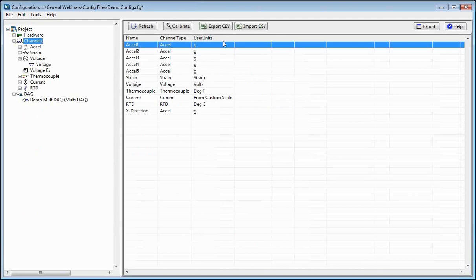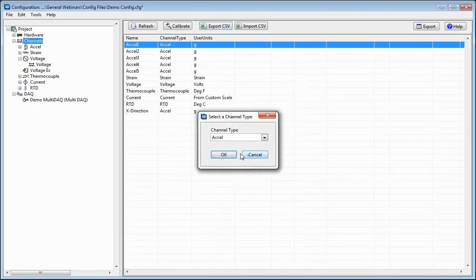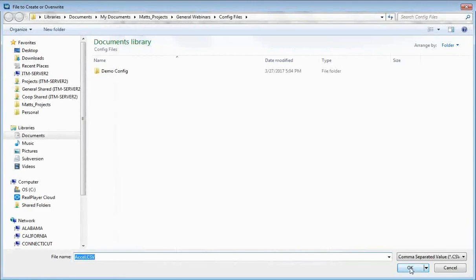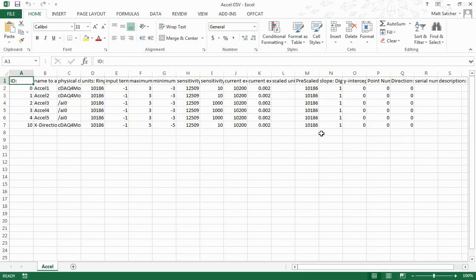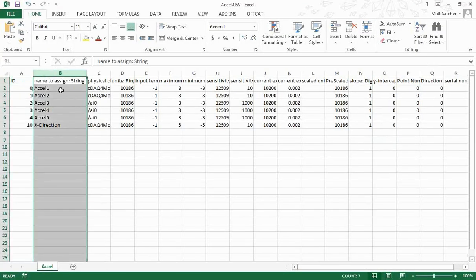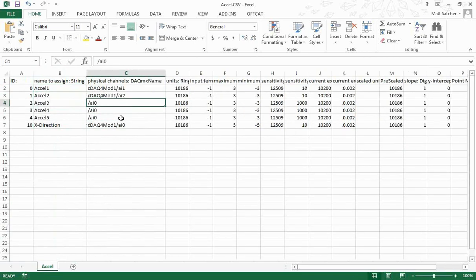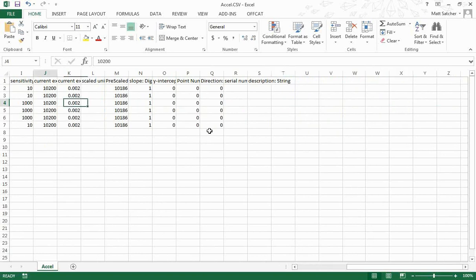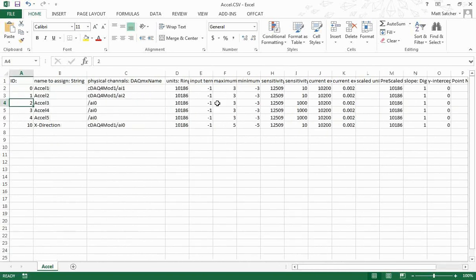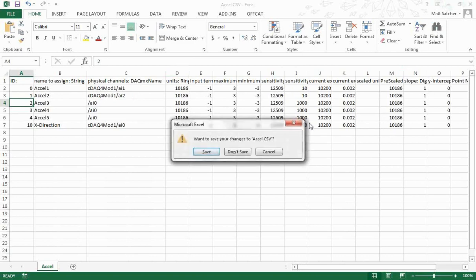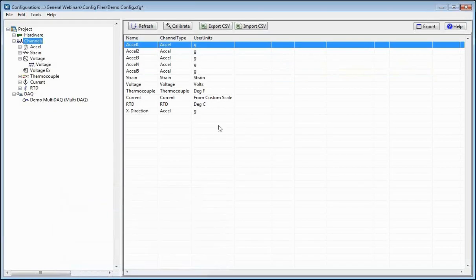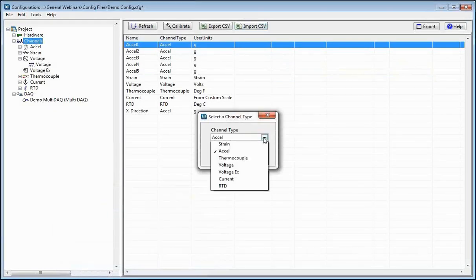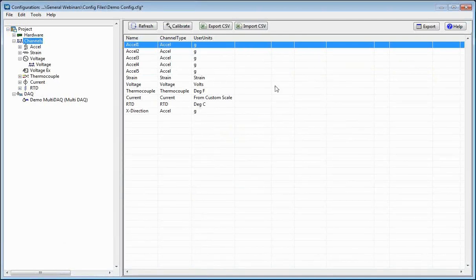Another thing you can do with channels is export and import CSV. If you just export the CSV for all your accelerometer channels, it's going to create a CSV file that pulls in all the accelerometer channels we've created. It'll show their physical location and all the sensitivity values, min/max voltage — all that information for any of your channels will be there. By exporting it out and making edits, you can fast-edit your accelerometer channels from a spreadsheet. Save that file, then go back and import the CSV, choose Accel, and it's going to update all of your accelerometer channels.